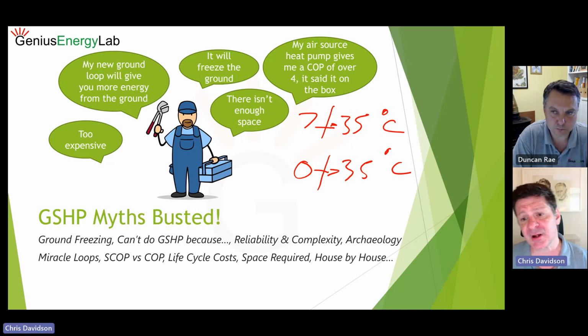Now in ground source, to come up with that seasonal COP is relatively straightforward, actually. The software will actually produce a seasonal COP as part of the design process. For air source, it's a bit more complicated because you've got to take account of not just the air temperature, but also the humidity in that air, because when you're heating, you are cooling down the coils on the outside of the building. You'd naturally get then condensation from that wet air, and that condensation will freeze, which effectively would stop the heat pump working. So it needs to defrost. And so proper consideration of that defrost cycle is very, very important.